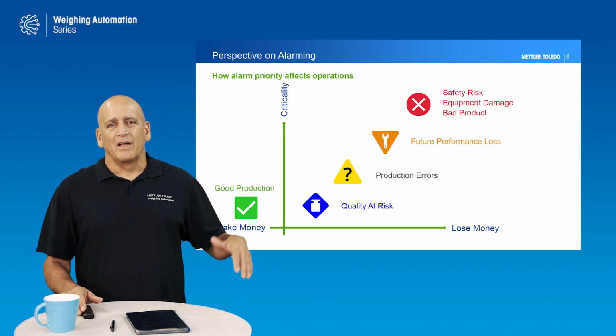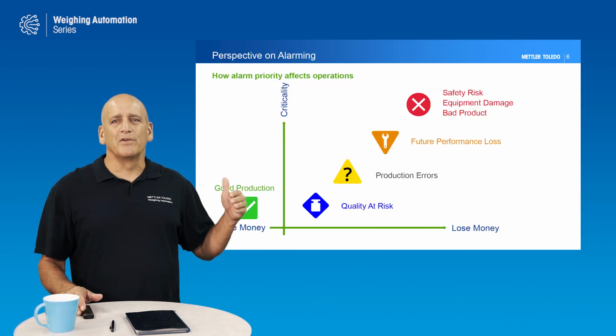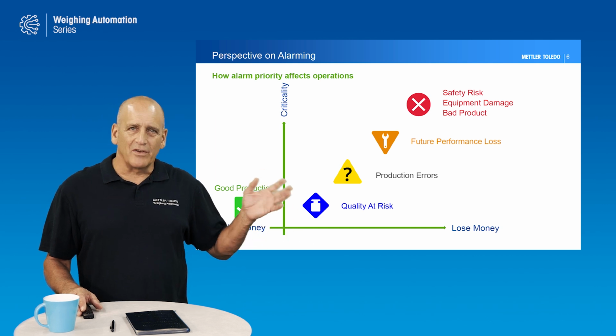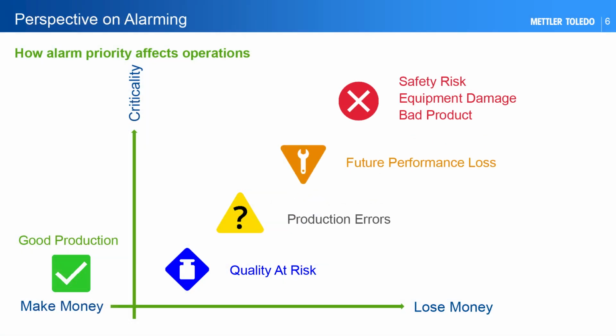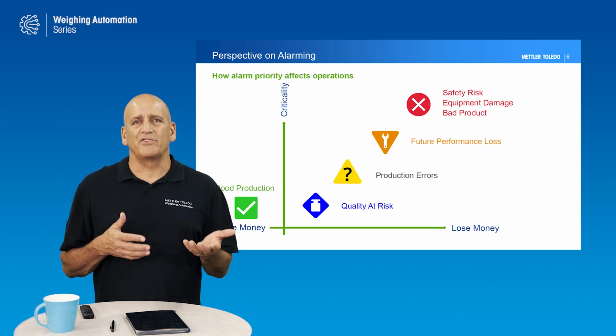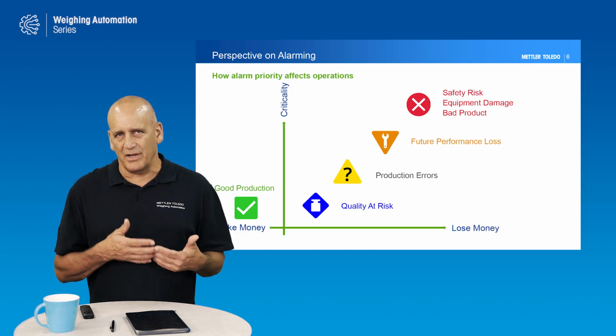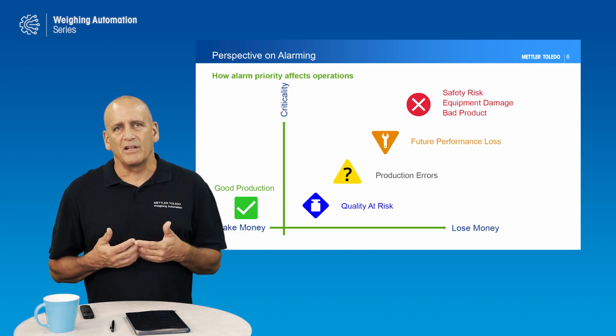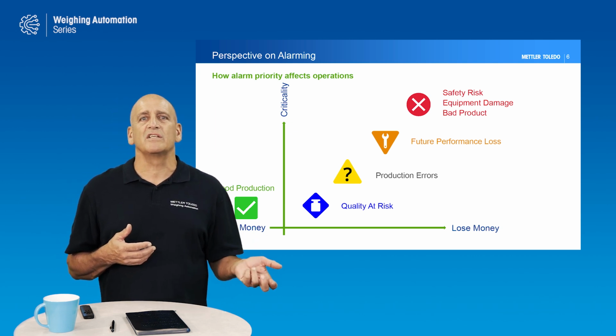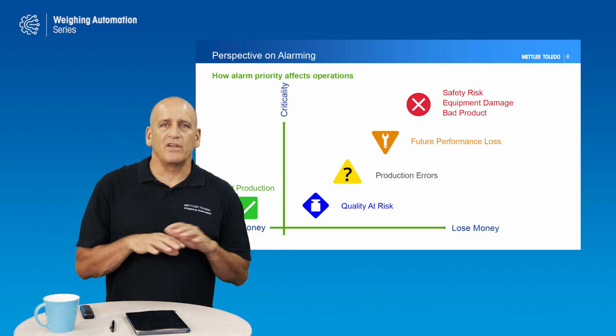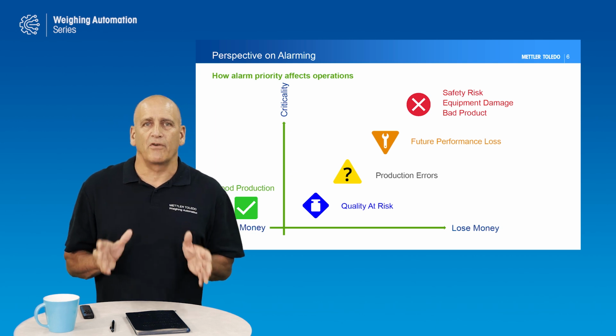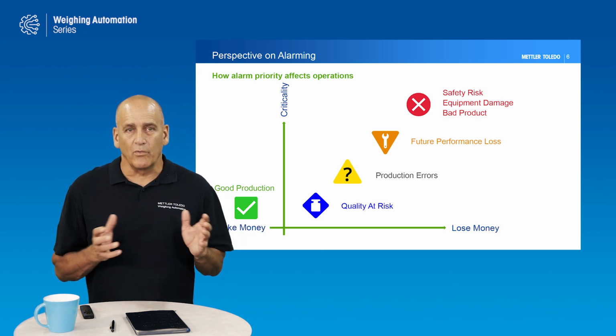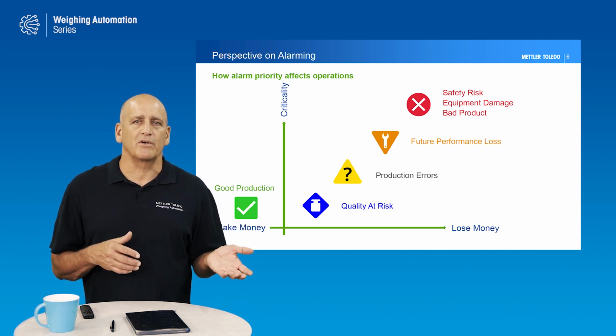So these 5 levels indicate that you're making money with green. Blue, the quality is at risk. The quality is still probably good, but it's at risk sometime. You might go out of tolerance. Yellow will tell you if you've got process missteps. If you have recurring yellow alarms, you might want to change something in the process to make sure that you don't have that. And as we said, the orange alarm indicates that service needs to be done, or in red, you need to stop the process because you know for a fact that your batch could be wrong or the weight is wrong and it could have a negative effect on your process.